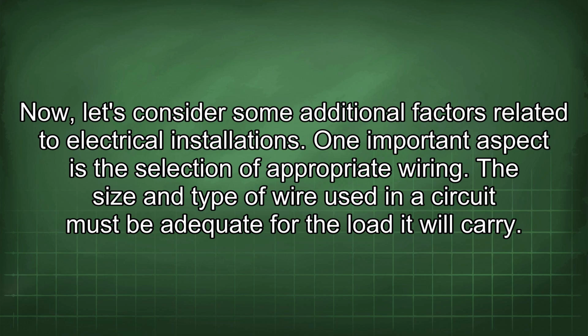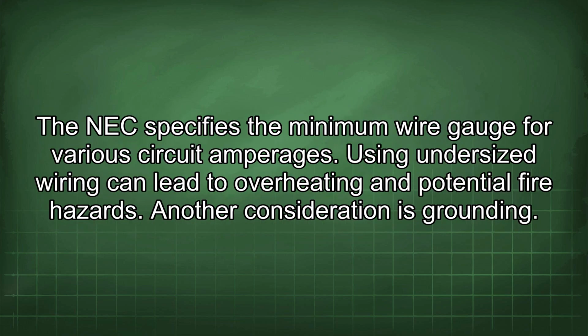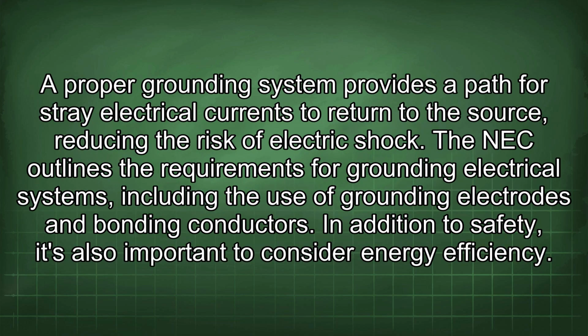One important aspect is the selection of appropriate wiring. The size and type of wire used in a circuit must be adequate for the load it will carry. The NEC specifies the minimum wire gauge for various circuit amperages. Using undersized wiring can lead to overheating and potential fire hazards. Another consideration is grounding. A proper grounding system provides a path for stray electrical currents to return to the source, reducing the risk of electric shock. The NEC outlines the requirements for grounding electrical systems, including the use of grounding electrodes and bonding conductors.